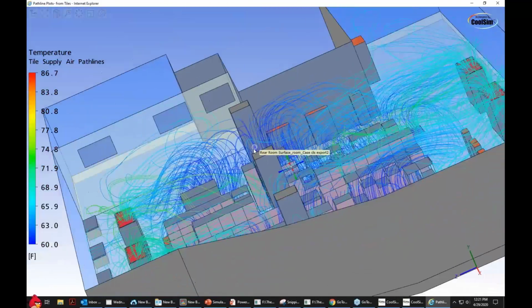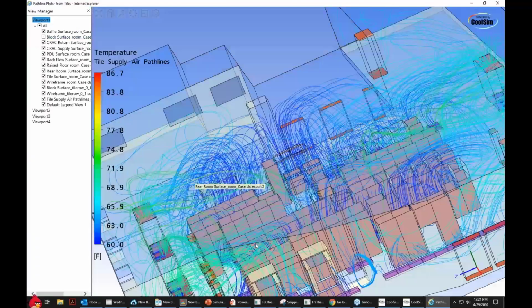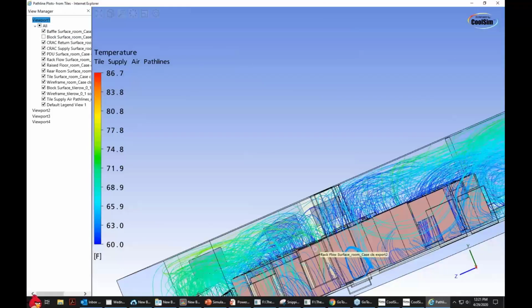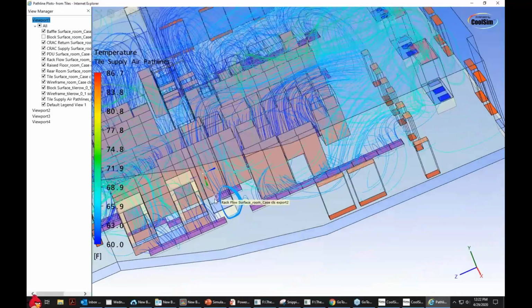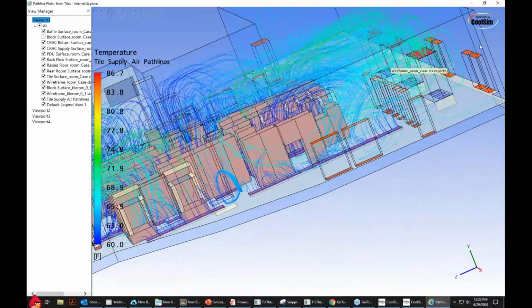This one's also unblanked, if you notice. And let's turn off that block so that we can see through the wall there. But you see there's holes in those racks. They didn't blank. So that's also a problem. So that one's got way too much air, and it's not in great shape either.